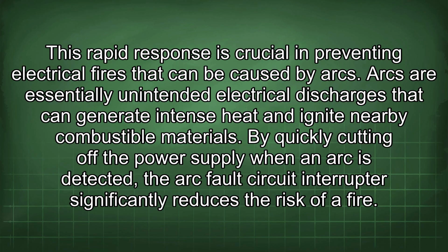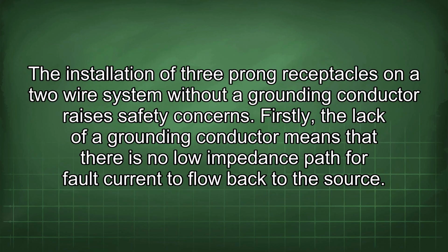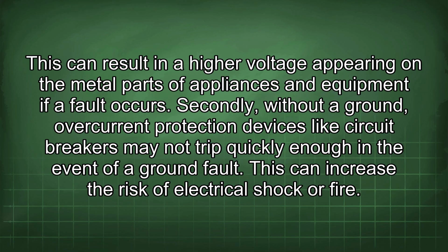The installation of three-prong receptacles on a two-wire system without a grounding conductor raises safety concerns. Firstly, the lack of a grounding conductor means that there is no low impedance path for fault current to flow back to the source. This can result in a higher voltage appearing on the metal parts of appliances and equipment if a fault occurs. Secondly, without a ground, overcurrent protection devices like circuit breakers may not trip quickly enough in the event of a ground fault. This can increase the risk of electrical shock or fire.